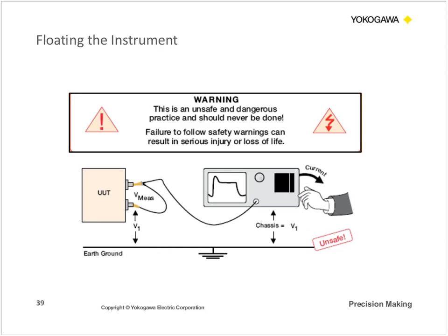If you float the instrument, what ends up happening is there's a voltage potential between the instrument and earth ground, and that voltage difference can be hundreds or thousands of volts. Any exposed metal or any accessible parts are going to carry that high voltage. So if you as an operator are touching that instrument and you power it on, that's a couple thousand volts that's going to be running through your body, which is definitely an unsafe practice. But this can also occur if you're connected to a cabinet or an enclosure as well.